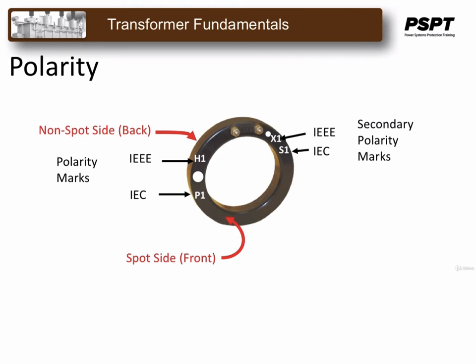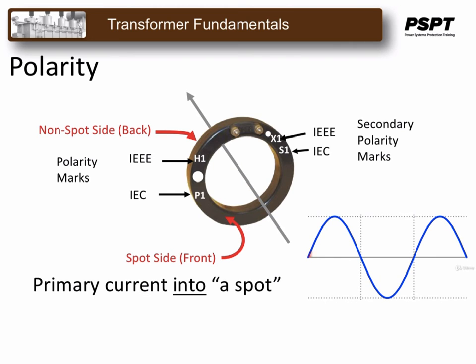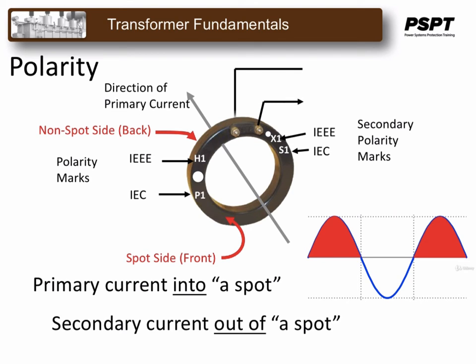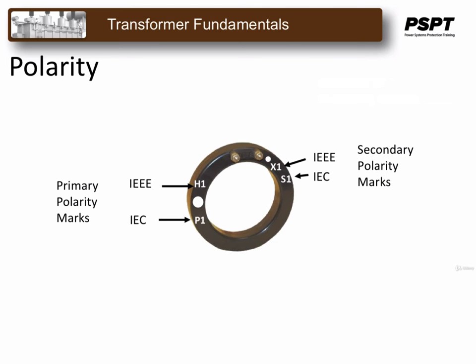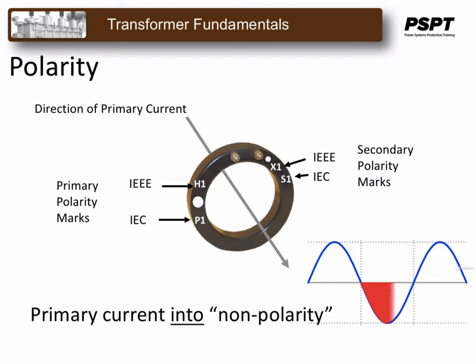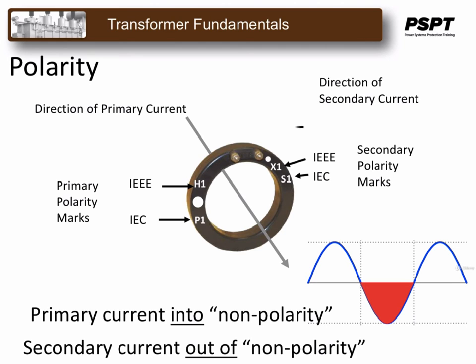What this indicates is that when the primary current is positive during the sinusoidal half cycle, current into the spot, the secondary current will be out of the spot. And what this also indicates is that when the primary current is negative during the sinusoidal half cycle, that is, the current out of the polarity spot, the secondary current will be out of the non-polarity spot.